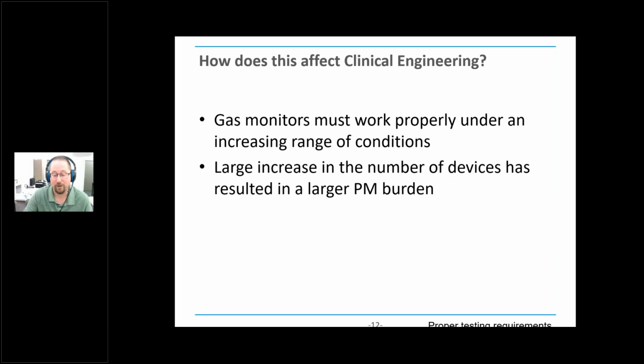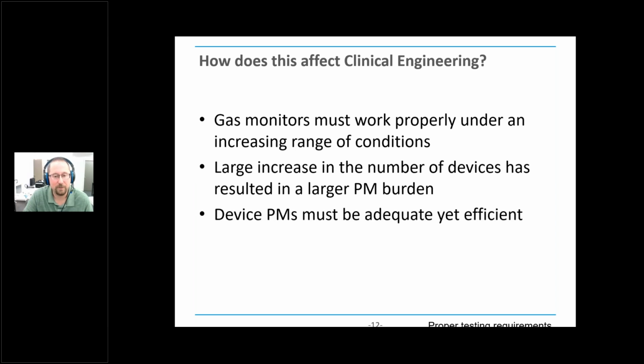It's also a larger number of devices in the hospitals. Some hospitals have hundreds of these devices now. And so now you have a much larger PM burden. You need to make sure that your PMs are adequate, that you're doing a good job testing, but you've got to be efficient to get through it all, because some of the PMs can be time intensive.